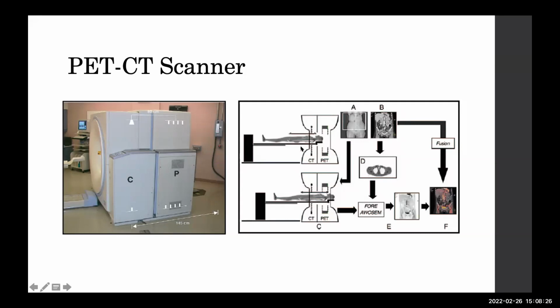This is the sketch of a PET CT. The patient first moves into the CT gantry, you acquire the CT data, and then the patient moves into the PET gantry, and you acquire the PET data. Now this CT data is used both for attenuation correction as well as for anatomical information. So the attenuation correction of the PET data is done with the CT morphological map of that particular patient, and this is the attenuation corrected PET image, and this is the fused image.